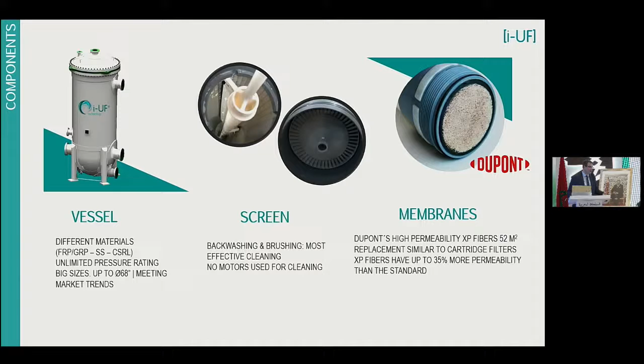We all know that the conventional ultrafiltration modules are packed in PVC housings or polyethylene or other thermoplastic material cases. This means that there are some limitations in terms of the usage of these modules. The FRP material is a thermoset one, while the PVC and other alternatives available in standard shape in the market are thermoplastics. The thermoplastics do not behave properly against a combination of heat and pressure. So this means another huge advantage for the FRP, that can be installed outdoors and can withstand higher pressure ratings, thus offering the possibility of playing in a smarter way in your favor when developing new projects or when trying to retrofit existing old installations.